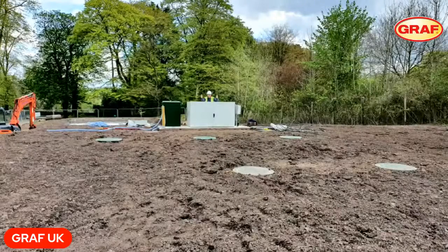In terms of the system supply, as I said, it's a 250 pop. Now, for us here at Graf, that's actually a 3-tank system. So it incorporates quite a large primary tank up front, where we basically collect all of our waste before then lifting it through into the reaction chambers, which were 2 SBR tanks, 1,000-litre tanks, to do the treatment process.